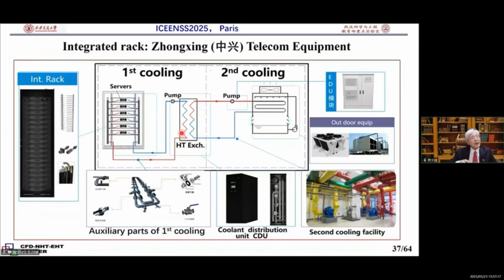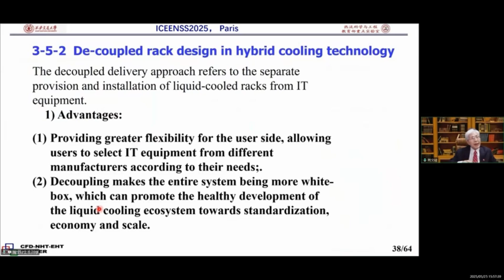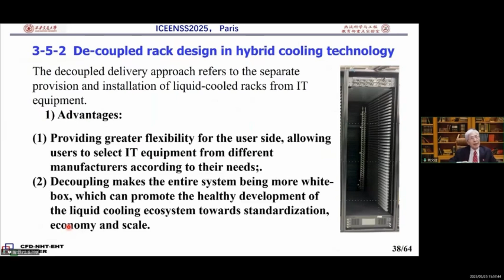And this is another integrated rack provided by ZTE, a telecom equipment maker. Now, another part is the decoupled rack design in hybrid cooling technology. It has two advantages. First, it provides greater flexibility for the user side. Second, decoupling makes the entire system more open, so it can move towards standardization, economy, and scale. This is the decoupled rack, which is open. And this is the front view of the decoupled rack. This one is filled with servers by users. And this is the air and liquid cooling system in the decoupled rack. This is the system for cooling air, and this is for cooling water.